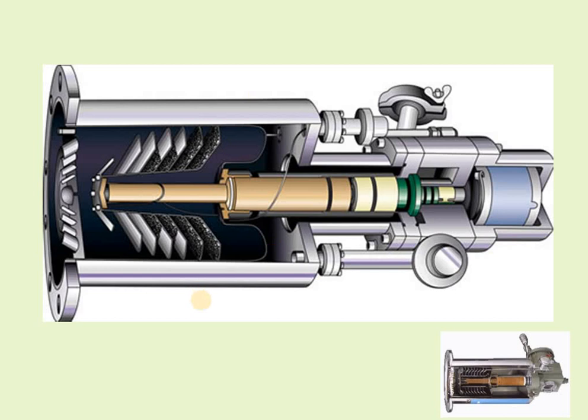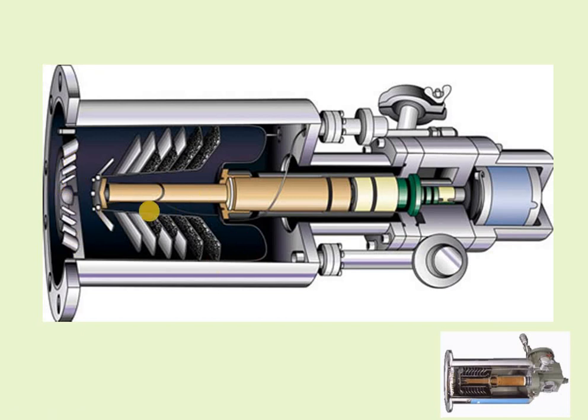This is a cross-sectional diagram of a cryogenic pump. You can see certain surfaces — metallic steel plates called cryopanels — at different sets. There are different sets of cryopanels that work in different stages, just like in a diffusion pump. There are different stages of working in a cryogenic pump.